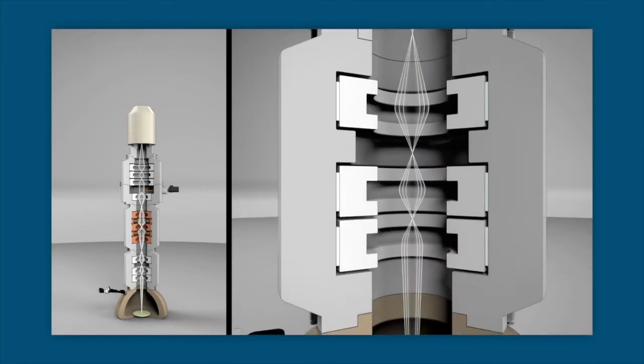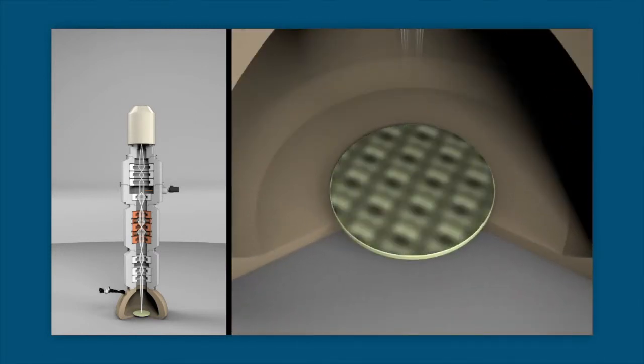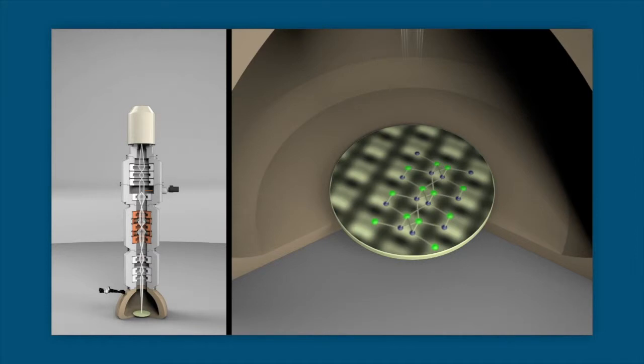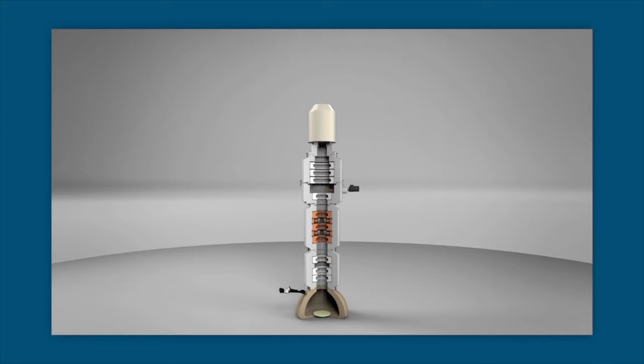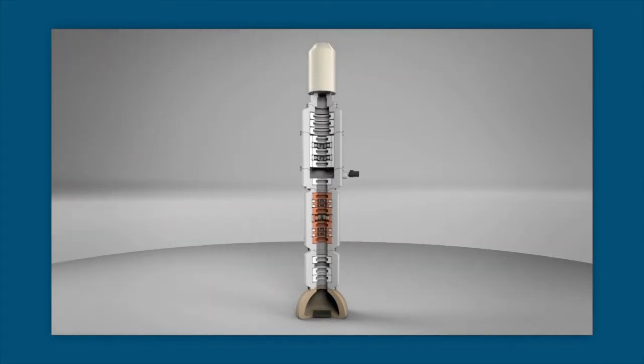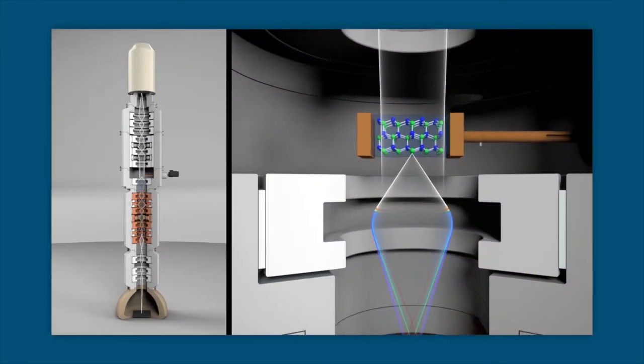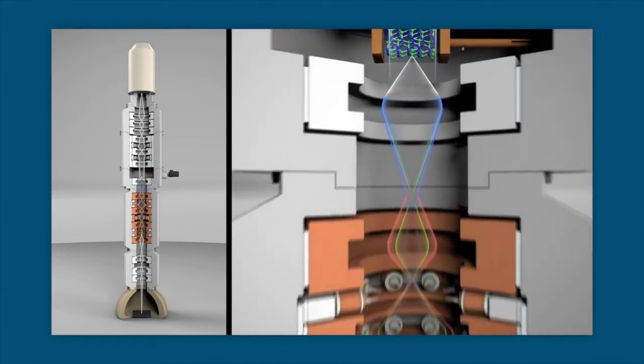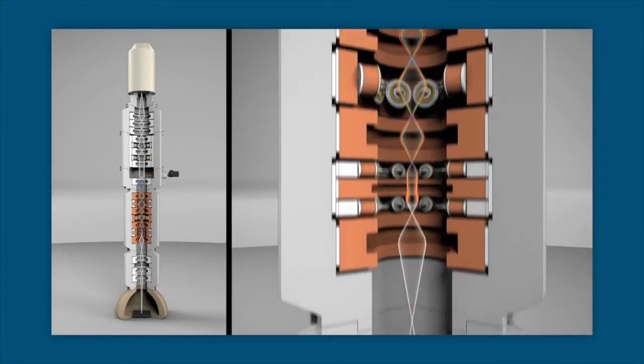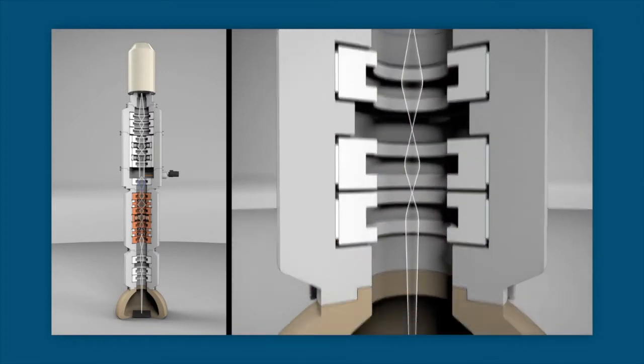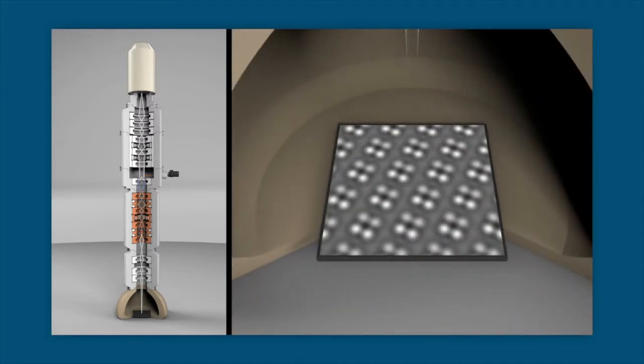In other words, the focal lengths of electrons that travel at different distances from the optic axis of the microscope were now the same, and the resolution was improved to better than the one angstrom level. Electron microscopy is a very rapidly developing subject, and the latest generation of instruments incorporates both chromatic and spherical aberration correction. Now the electrons which have different energies also have their focal lengths corrected, and in the most modern generation of electron microscopes the spatial resolution is improved to close to the half angstrom level.